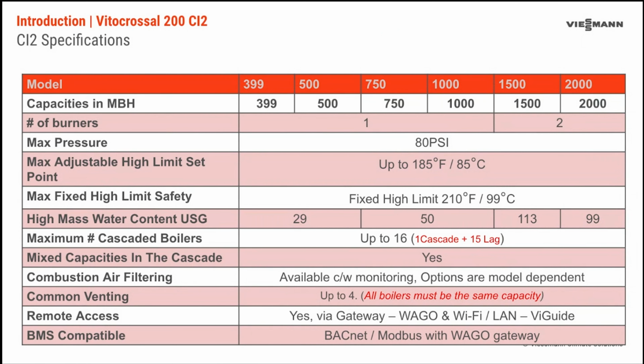We're going to look at some key points here. So the 399 through 1 million, we can refer to as a single boiler. So one burner and one heat exchanger. As we get into the 1.5 million and the 2 million, they get considerably taller, but maintain the 29.5-inch width. And in order to do this, what we've done is we've stacked 2 boilers. So the 1.5 million is a 1 million boiler on the bottom and a 0.5 million on the top. And when we have the 2 million, we have a 1 million boiler on the bottom and a 1 million on the top.